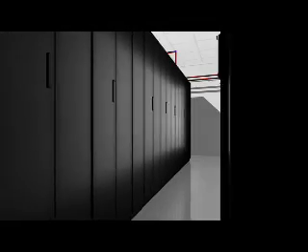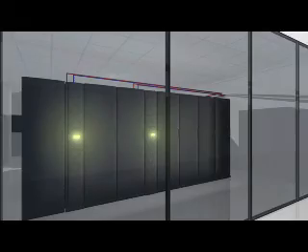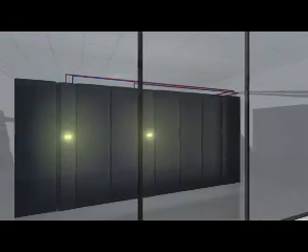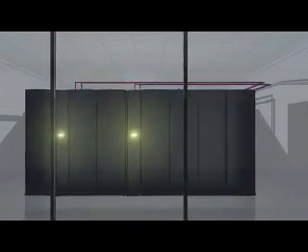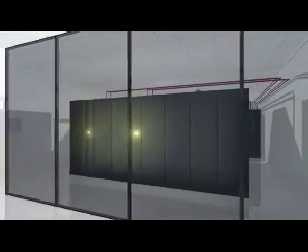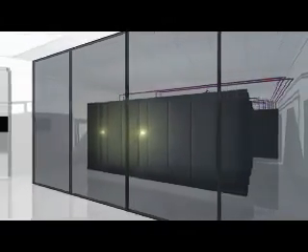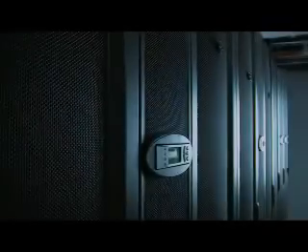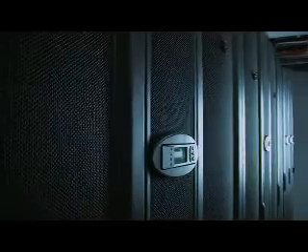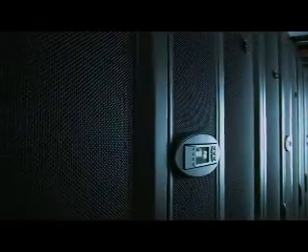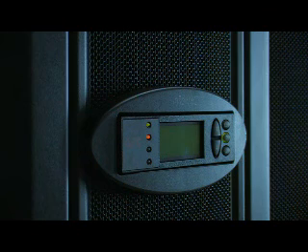The cooling units are installed between the racks and have now been configured for a medium density environment. However, the design allows for a simple and easy expansion of the system for densities up to 20 kilowatts per rack. The in-row cooling units extract heat from the hot aisle and deliver cold air in the cold aisle.